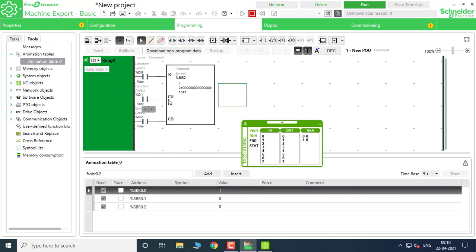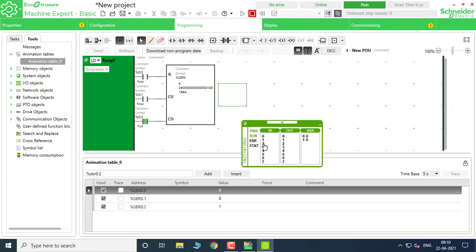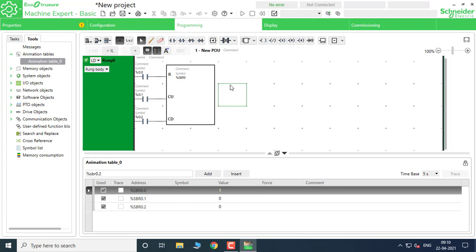When I toggle Count Up with I0.1, you can see the bit shifts to the next position. Toggling Count Up keeps shifting the bit to the left. To count down, I use I0.2, and pressing that brings it back to the previous positions. That is the Count Up and Count Down behavior of the Shift Bit Register. You have to set a 1 in the first memory bit of the SBR. R means Reset.